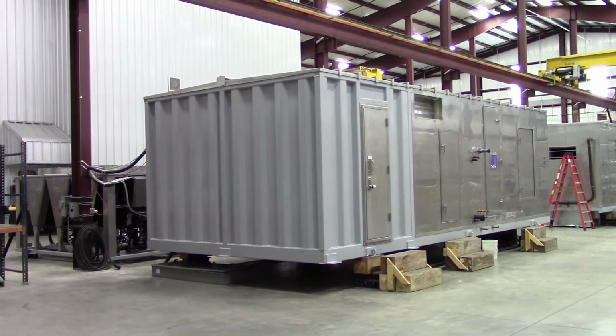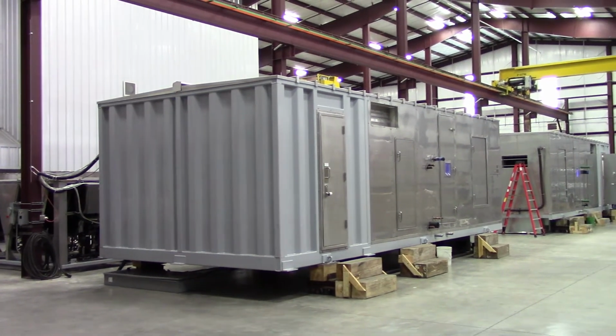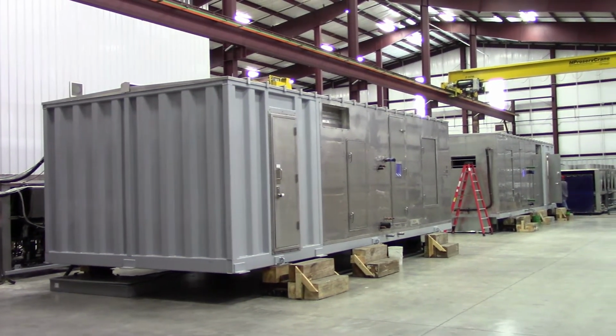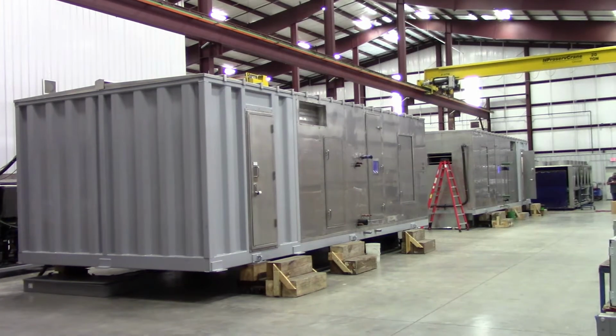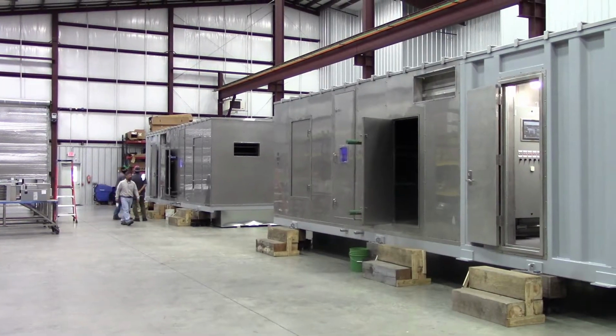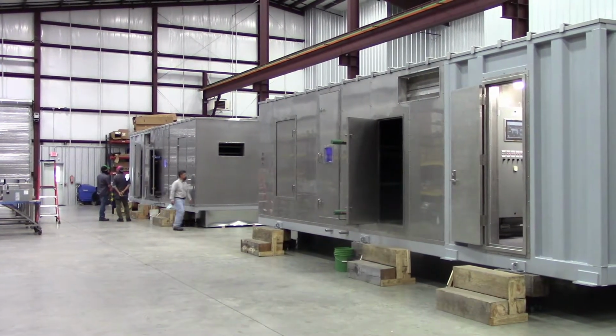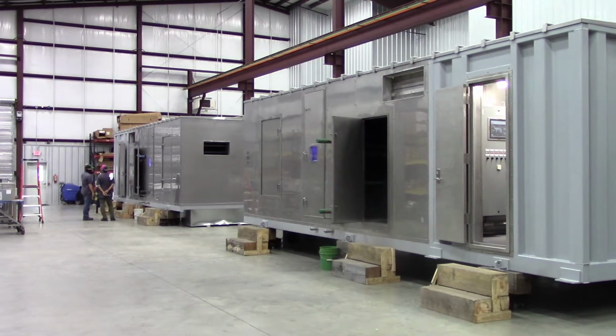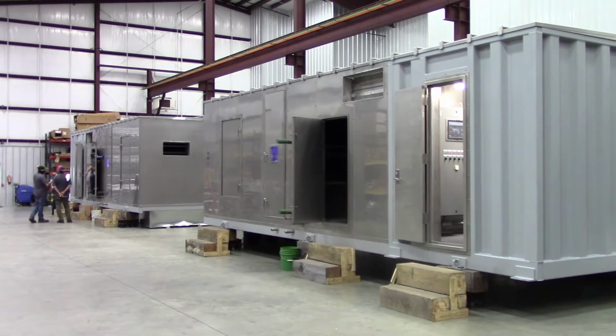So we had to make the unit wider and create a fresh air tunnel inside the unit. It turned out to be a very compact design. We ended up with 160 tons in a small footprint, and the air handling unit is blast rated up to 0.5 bar.